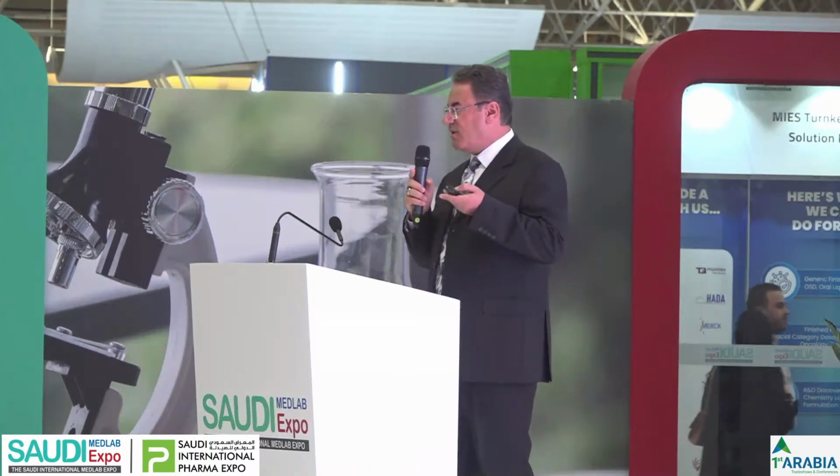Now, for a new QC lot, whether in hematology or chemistry, do you verify or establish the ranges, and how? And here I'm talking about quantitative analysis, not qualitative. Qualitative, that gives you positive or negative, you can use without any verification. You just use it as is.